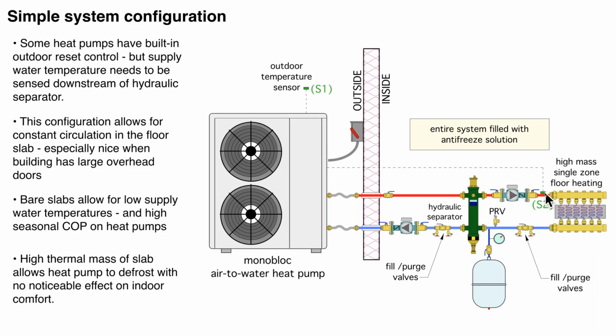So we've got constant circulation in the floor. As the temperature at sensor S2 starts to drop slightly below the target value, and the target value is constantly being calculated by the outdoor reset controller based on the settings as well as the current outdoor temperature, if it sees that temperature dropping slightly below the target, it's going to turn the heat pump on. So we're going to inject heat into our thermal mass. And once that sensor temperature rises perhaps 2 or 3 degrees above the target temperature, the heat pump's going to shut off. So it's a really simple system.